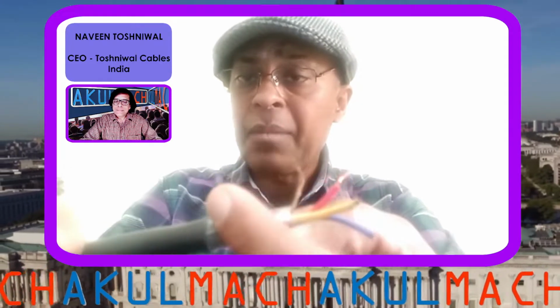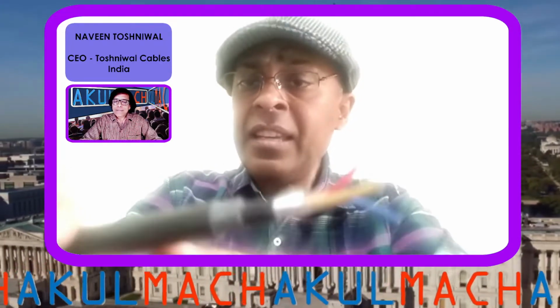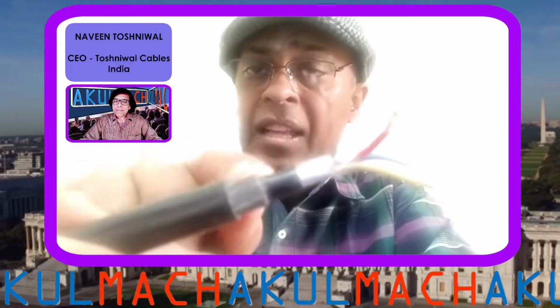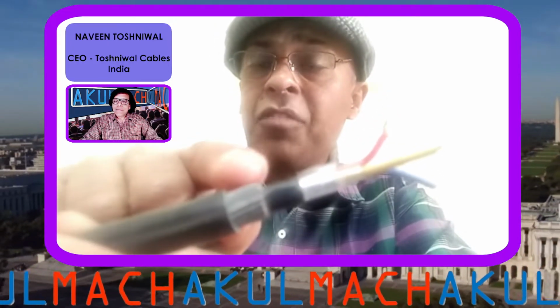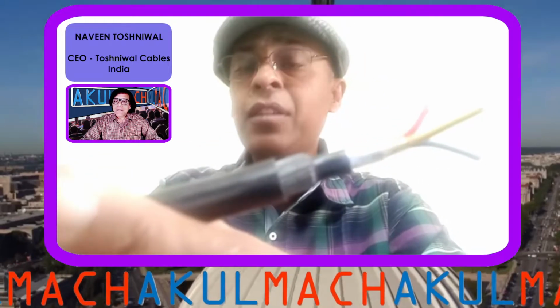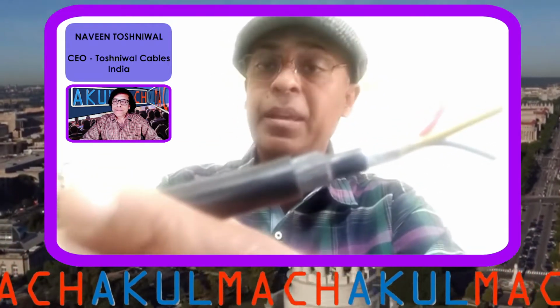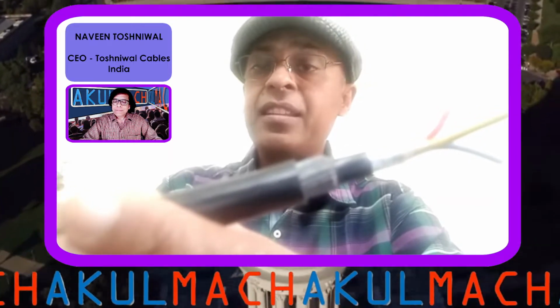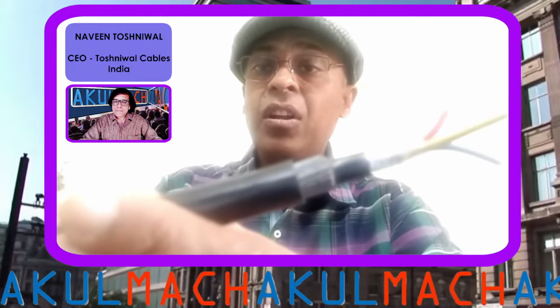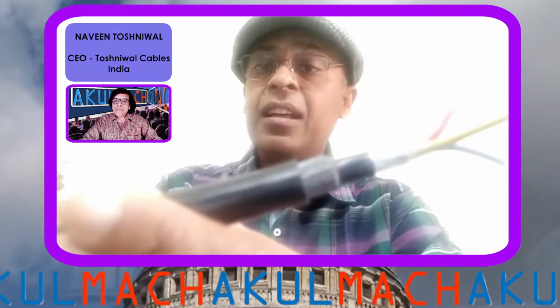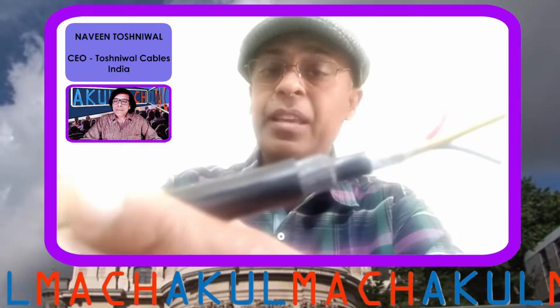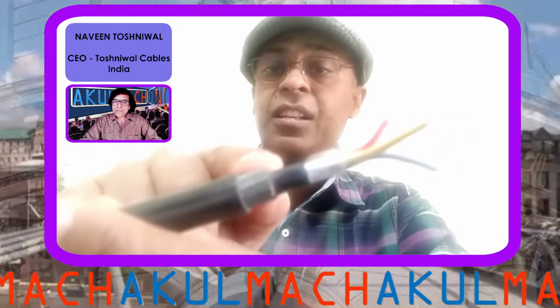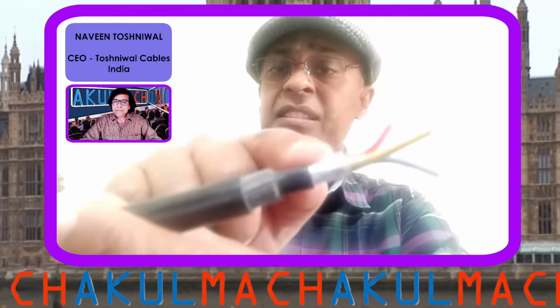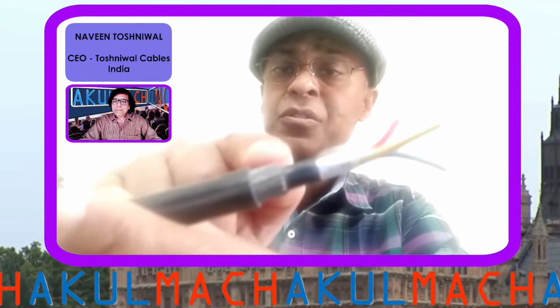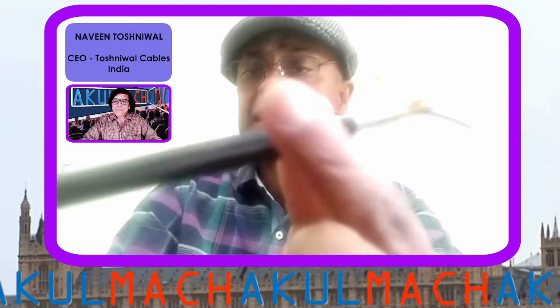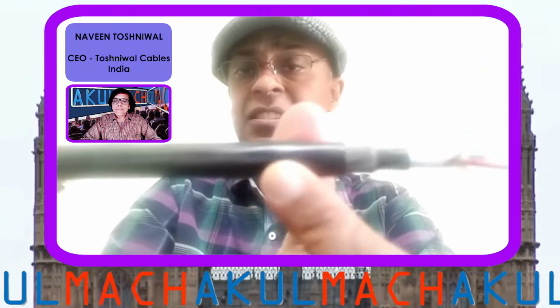This is the armor. Armor is basically made of wires, made of GI, galvanized iron, and it is used for providing mechanical strength to the cable. So if the cable is laid in a place where there are chances of people stamping on it, or a chance of mechanical disturbance or pressure on the cables, then this armor is essential. You will see that there is a PVC sheath before the armor, which gives the base for putting the armor. And then this is the final sheathing of the cable, which finishes the entire construction.